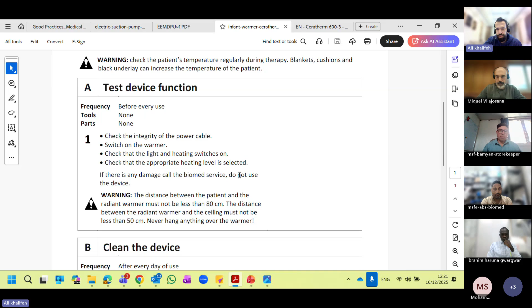Clean the device after each use using lint-free cloths and surfanios alcohol disinfection. They need to unplug the device before cleaning, for safety, and do this after each day of use as the frequency of cleaning. Here is the description of how to clean: clean the front panel, the switch, the connectors, the trolley, but do not wipe the top grill. We put the surfanios on the cloth and clean with that, not put the surfanios directly on the machine.